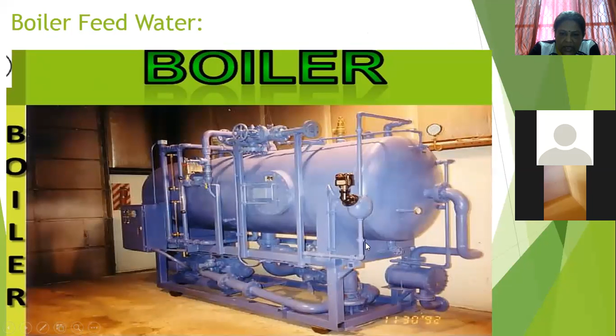Scales and sludge are formed due to the presence of salts in water. The salts present in water can be calcium and magnesium chlorides, sulfates, carbonates and bicarbonates. So if you are feeding the boiler hard water, or water which is not soft enough and contains salts, then as the water evaporates from the boiler, the water becomes enriched with the salts, and these salts slowly get precipitated over the boiler walls, boiler pipes, inner tubes, various rivets. The structure of the boiler, as you have seen, has many pipes, many portions and many joints. So each part of the boiler gets affected by the salt deposition.